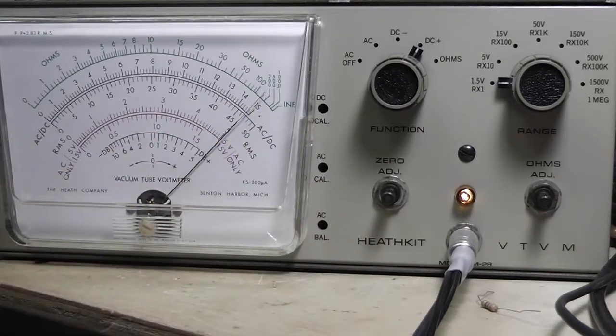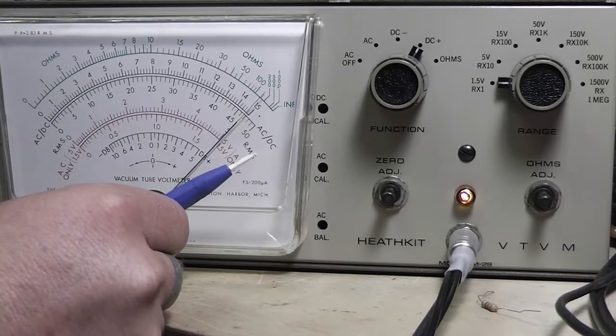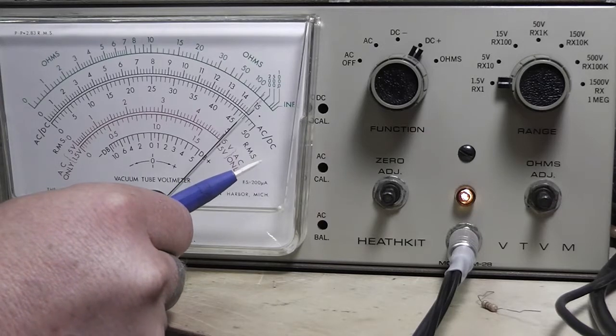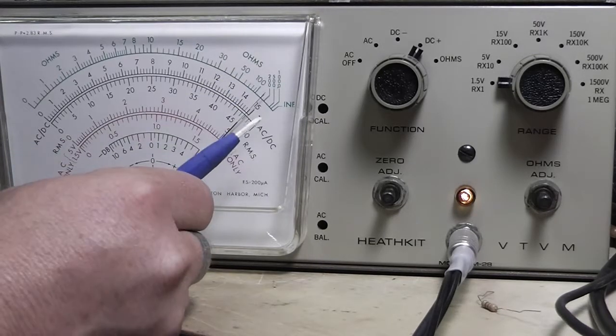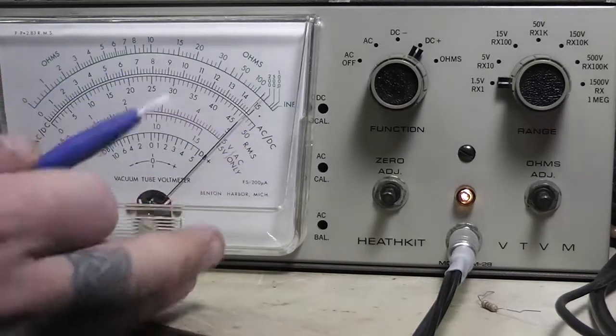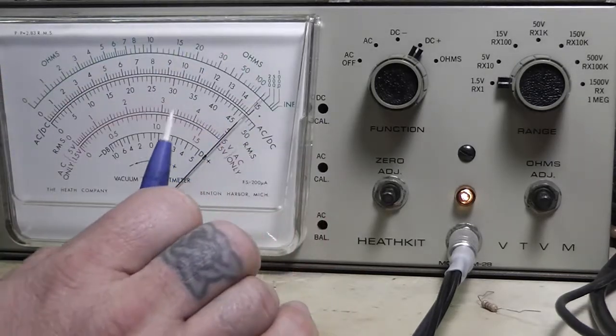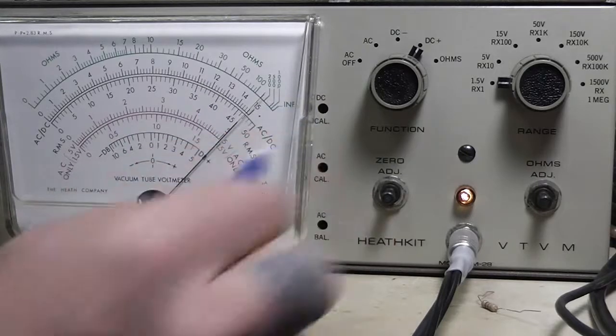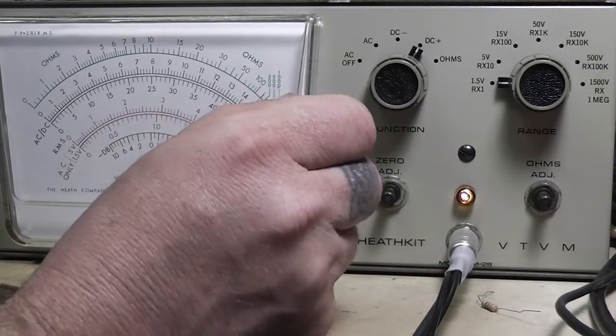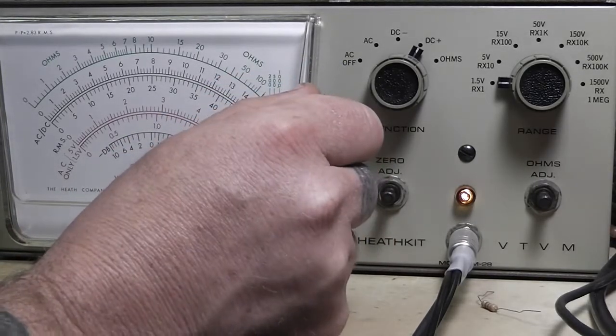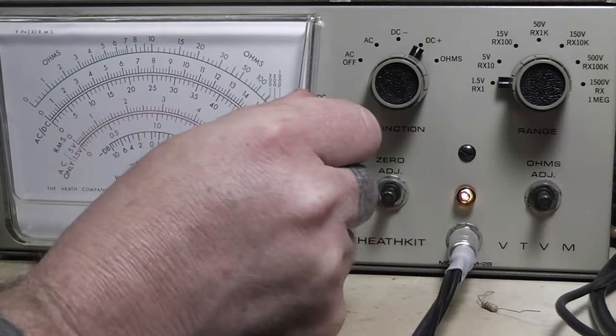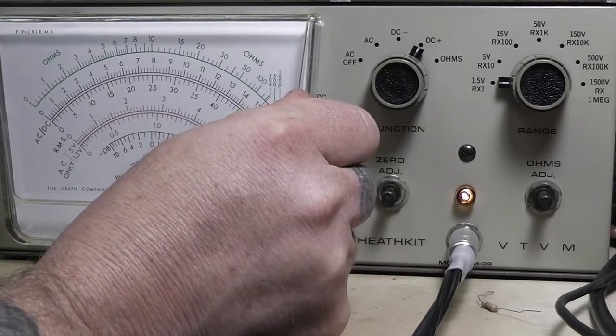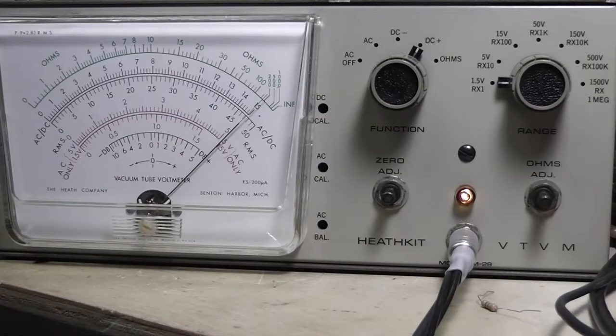When you use the red dot with the battery, you're close, but you're not exactly on it, because most fresh batteries are 1.6 volts, the reason that red dot's past there, on these 1.5 volt batteries. But if you hook it up, if your battery's 1.55 or maybe it's 1.5 and you're up there, then you're going to have your calibration off. So with the good power supply, I'm going to adjust that. I'll move my hand just a second. So they're at 1.5 volts.